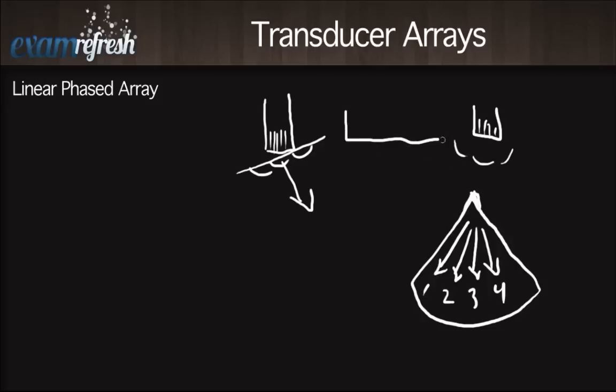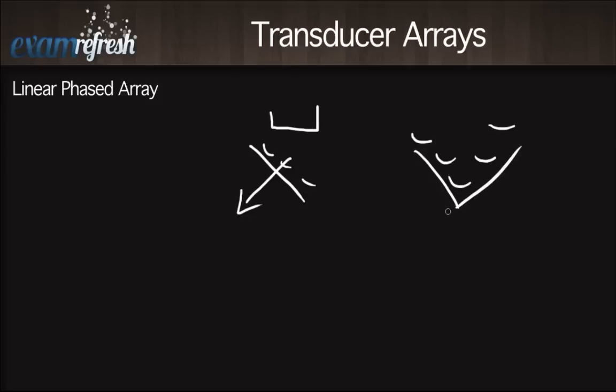The benefit of the linear phased array is its very small footprint, making it easy to get into small spaces — for example, imaging the neck of a baby where a four-centimeter linear transducer wouldn't fit. The phasing also allows the beam to be steered and focused. This was one of the first applications of the phased array: the ability to focus the beam and manually select the focal zone, compared to older fixed-focus transducers where you just hoped the target fell in the focal area.